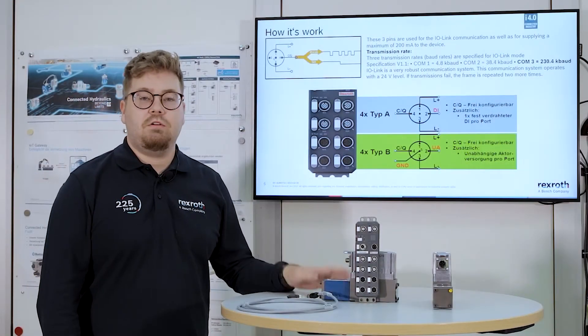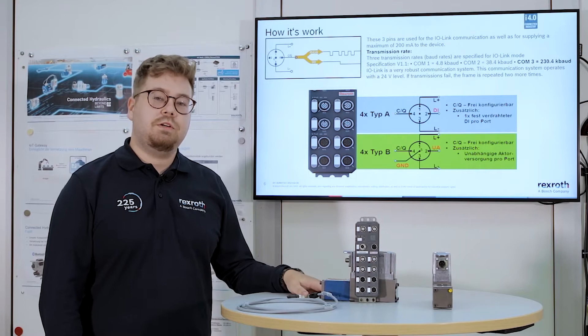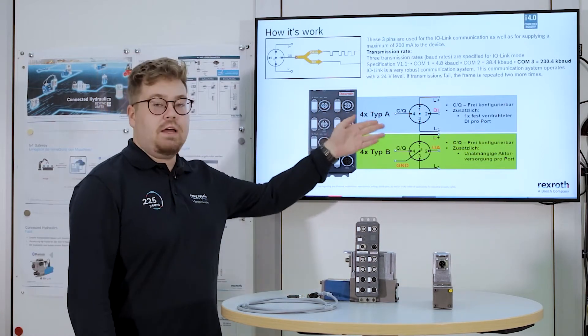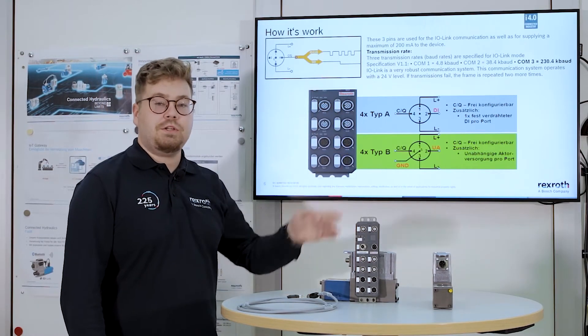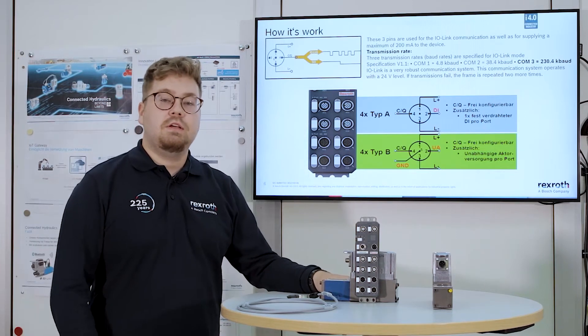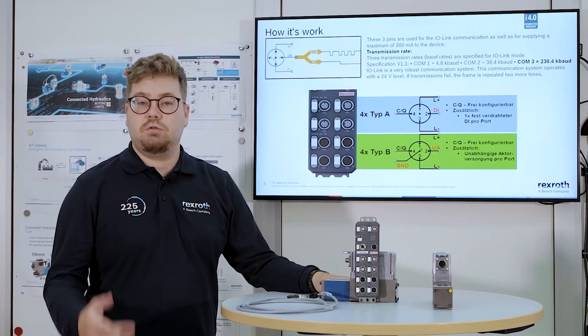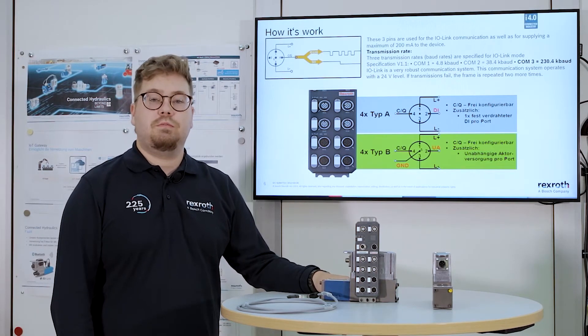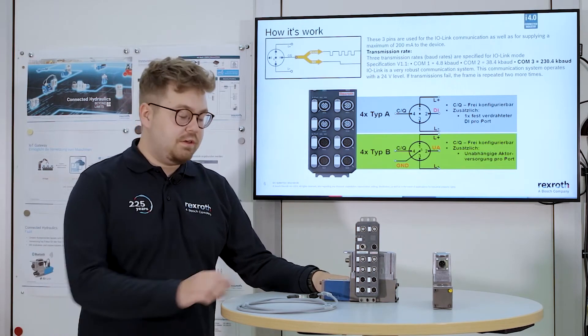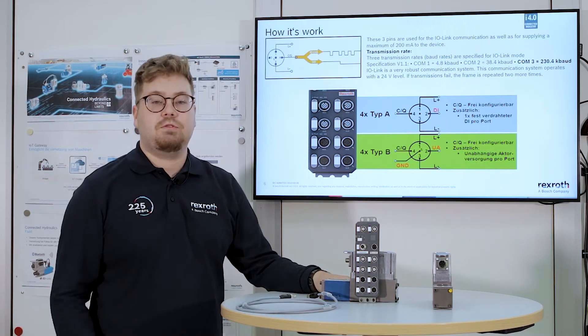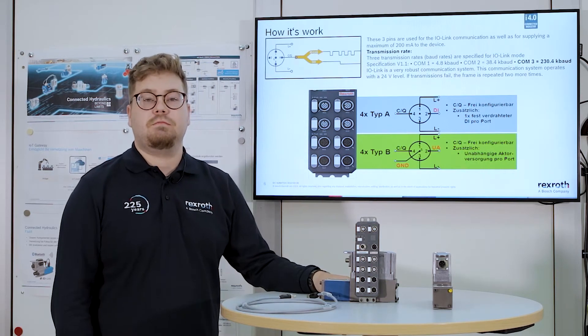Regarding IO-Link, we have to distinguish between a class A port and a class B port. For our valves we use the class B port, since besides the two-way communication we also ensure the supply voltage with this single 5-wire M12 cable.